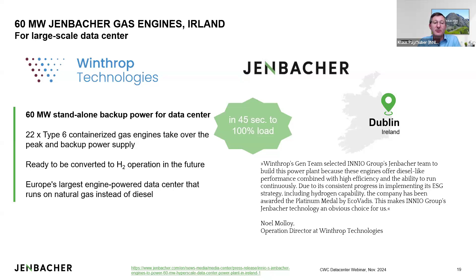That was the entry now to larger data centers, standalone data centers. In this case, it's a data center in Ireland, our first large data center application with a 60 megawatt backup solution. Here, the backup solution replaces diesel engines with gas engines. We supply 22 Type 6 engines, a containerized, highly standardized solution, and this engine can start in 45 seconds to 100% load.